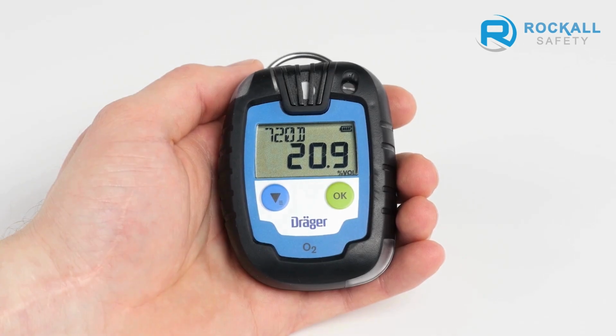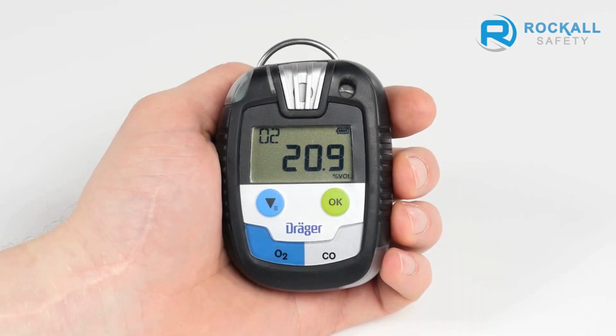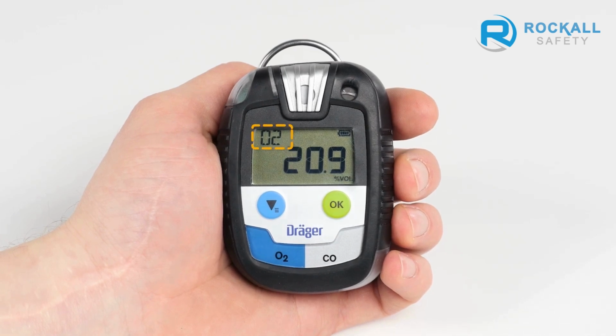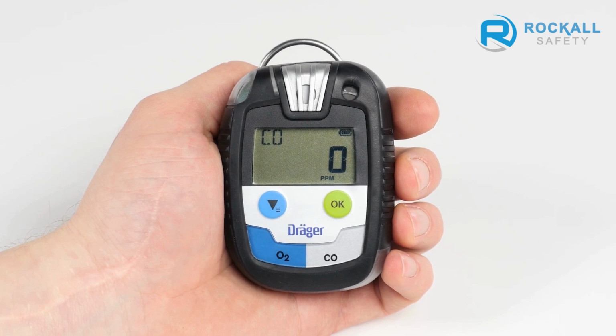On all devices, the standard screen indicates the battery level and the gas concentration. In addition, the time-limited PAC 6000 indicates the remaining operating life in days. Whereas all the other devices in the PAC series indicate the gas currently being measured. The Dräger PAC 8500 with dual sensors also has a special feature. The display indicates the gases alternately.